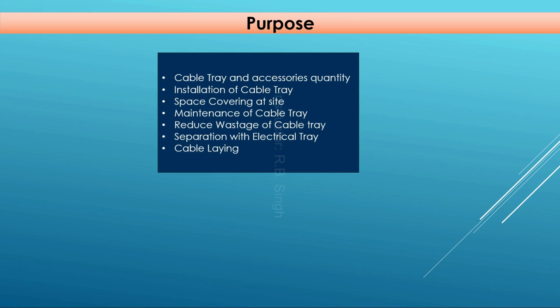You might wonder: if we are preparing a 3D model, can't we understand bends, expanders, and ups and downs of the cable tray easily there? Yes, but construction and installation cannot be done using a 3D model, because at site you can only take plain paper — you cannot take a laptop or systems everywhere in the plant. The best way for construction and installation of tray is based on 2D dimensional drawings, so we need to prepare detailed 2D drawings that any site engineer can use to install the cable tray.